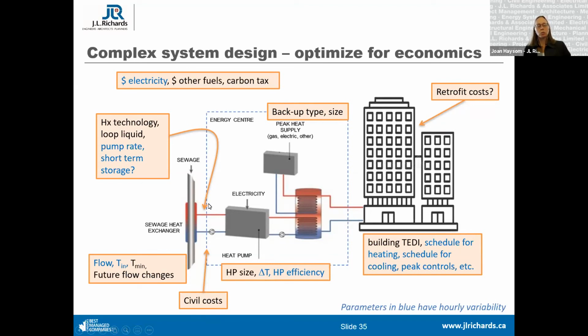There are details in this working fluid pumping loop, and a lot of details around the building itself - its schedule for heating, its schedule for cooling, and whether we're going to retrofit it. If we're bringing cooling in, do you have to build a new cooling loop that's not there already? Does that count into the economics? It's going to vary project by project where your boundary of what's included in the cost comparison should be. But it's really got to be done with total return on investment or life cycle cost analysis, not just capital cost, not just operational cost, but the whole package.